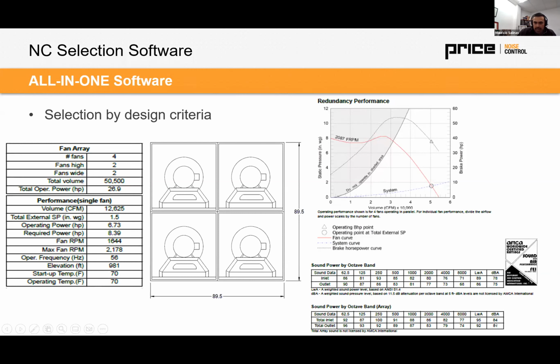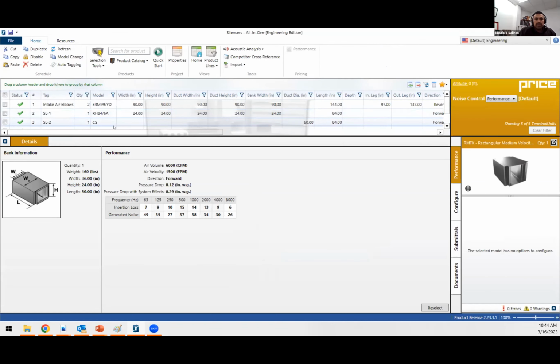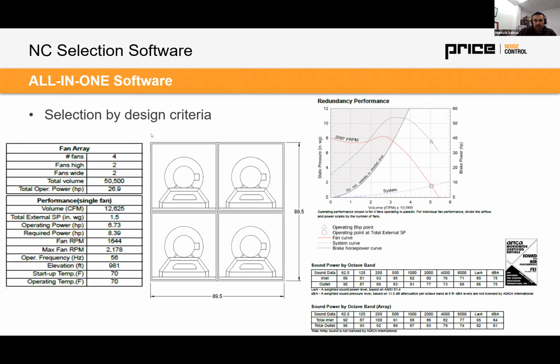So that unit at 5 feet is at 81 decibels. Exposing the human ear to over 80 decibels for prolonged periods of time is going to induce hearing loss, so you don't want that. You want to bring those down. So in that specific scenario, you might want to use a silencer that covers that entire area. You might want a 1 to 2 feet duct extension and then a silencer that's about 90 inches by 90 inches with 50,000 CFM.